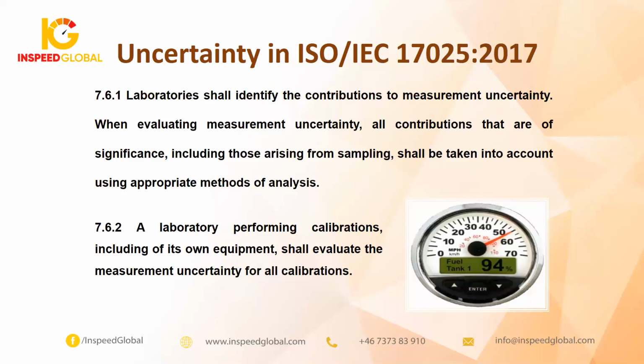The laboratory shall identify the contributions to measurement uncertainty, and when evaluating measurement uncertainty, all contributions that are significant, including those arising from sampling, shall be taken into account using appropriate methods of analysis. Also, 7.6.2: a laboratory performing calibration, including of its own equipment, shall evaluate the measurement uncertainty for all calibrations. So, my dear, for calibration laboratories it is mandatory to estimate uncertainty, and also mandatory to mention the results of uncertainty in their calibration certificate. And this is the difference between a calibration lab and a testing lab.